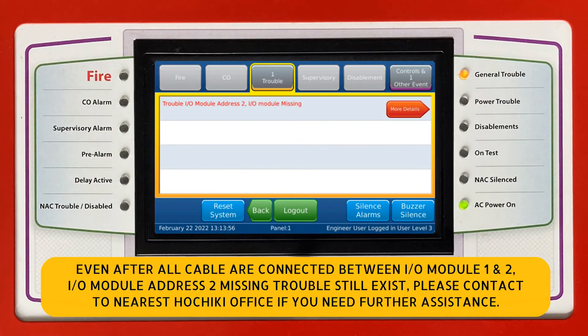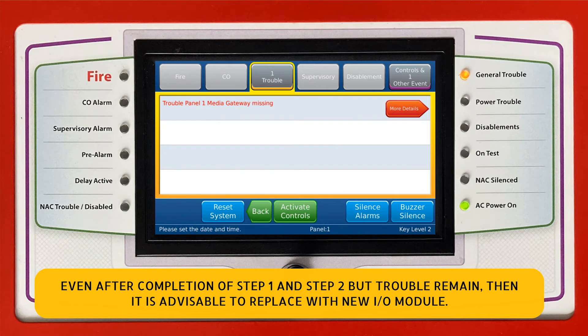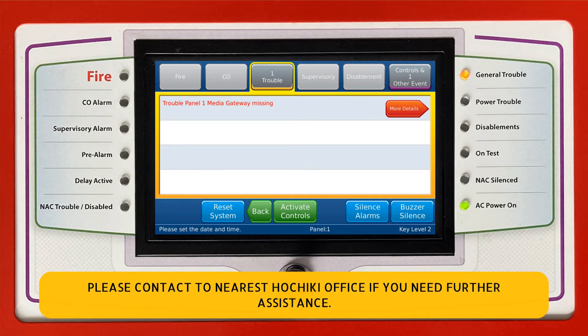Even after all cables are connected between I.O. module 1 and 2, if the I.O. module address 2 missing trouble still exists, please contact the nearest Hochiki office for further assistance. If trouble remains after completing steps 1 and 2, it is advisable to replace the unit with a new I.O. module. Please contact the nearest Hochiki office if you need further assistance.